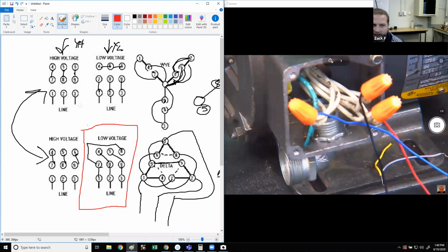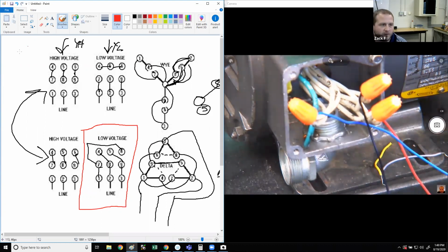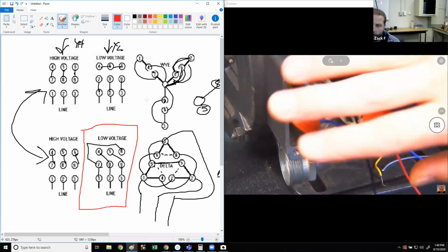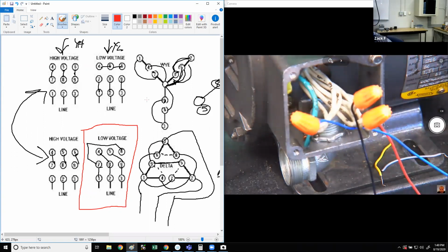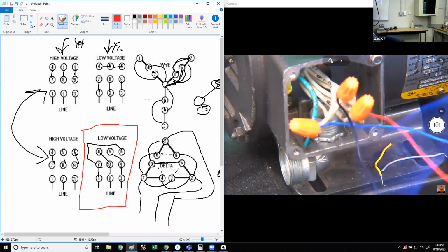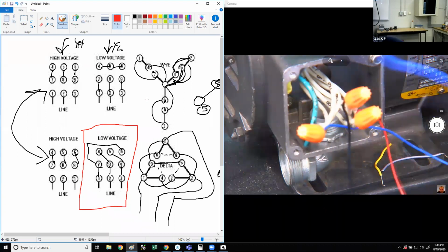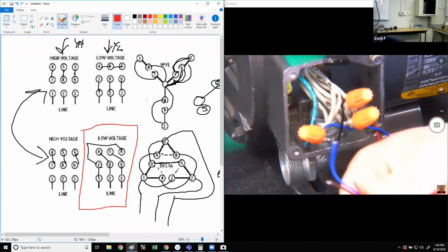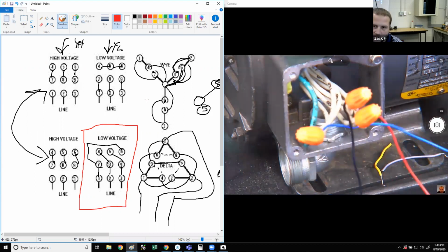All right. I just wanted to do that so you guys could see, because a lot of times I've taught this in the past where I'm just showing you how to make the connections with delta Y and delta low. And it's like, well, why the hell are we making pictures of this? Well, that's how we're actually hooking it up in here. Keep in mind, though, please don't ever just use wire nuts in a peckerhead. If I hook these 3 up to 208, I can get it in the picture. If I hook these 3 up to 208, it'll spin that motor, you know, but that's not how we do it.